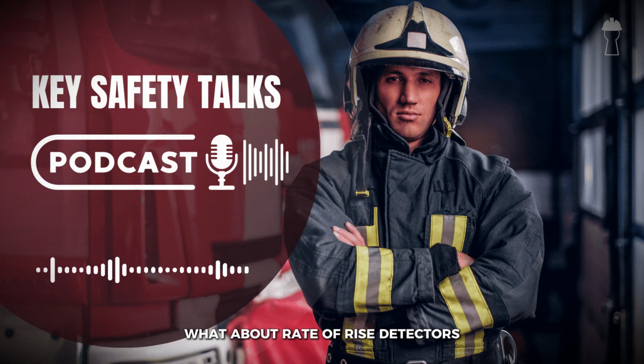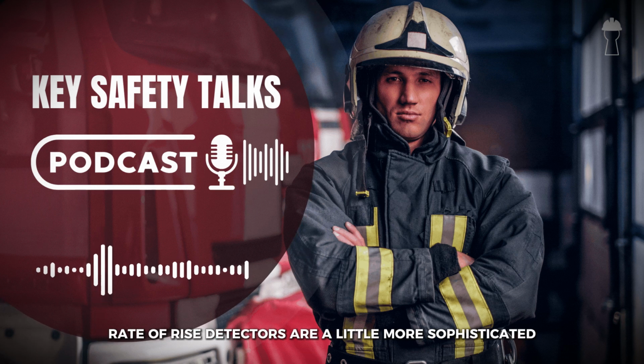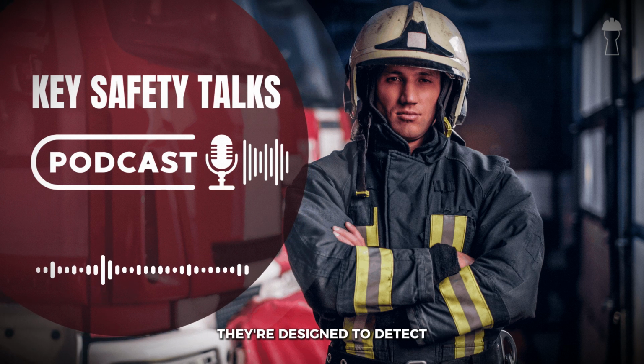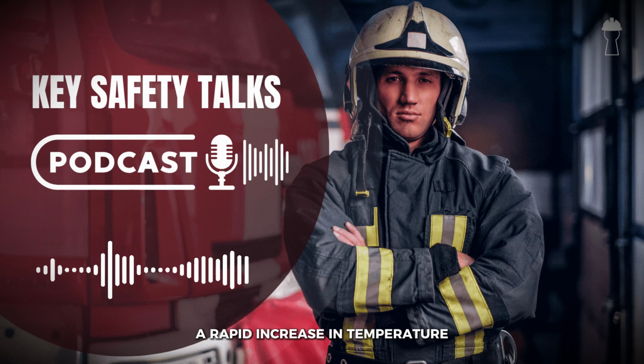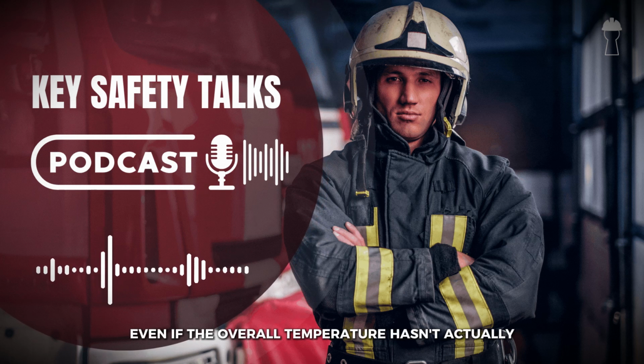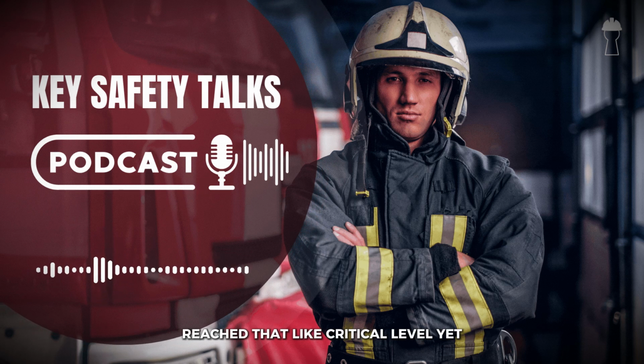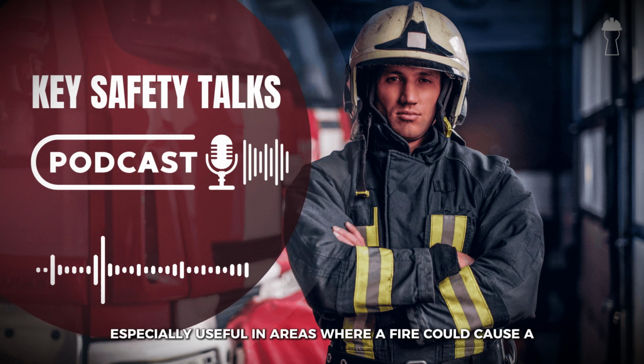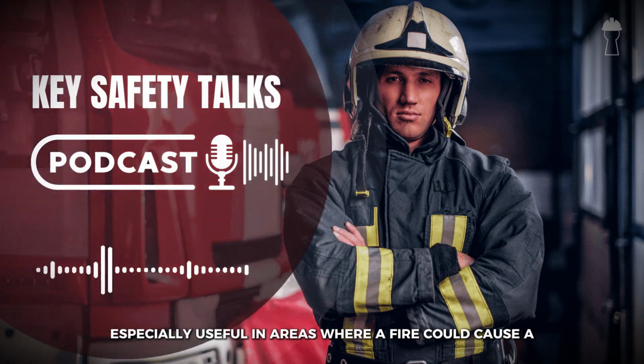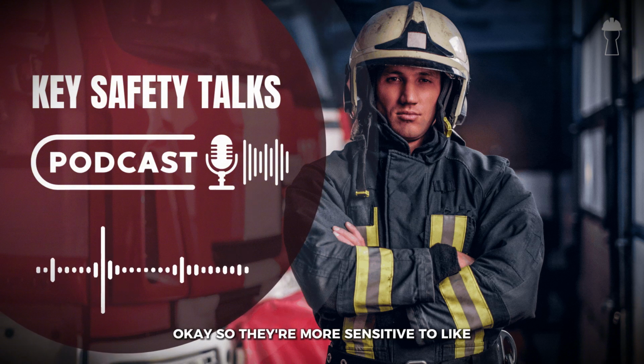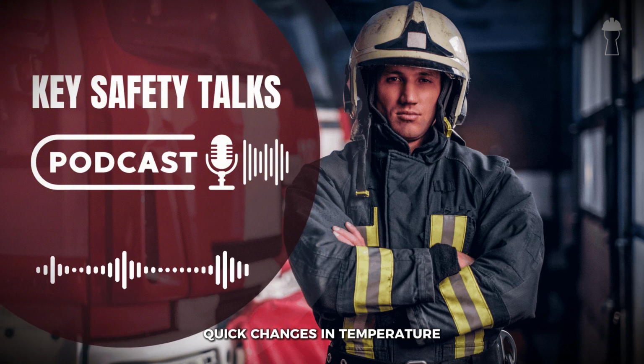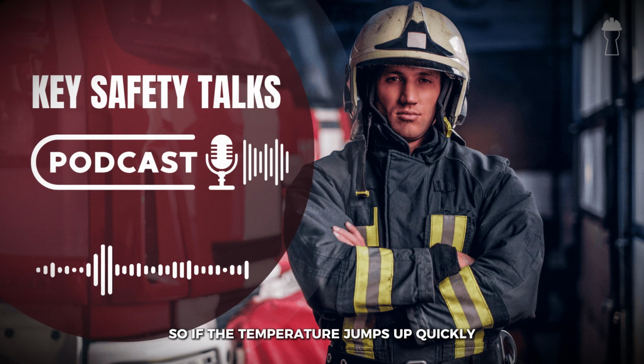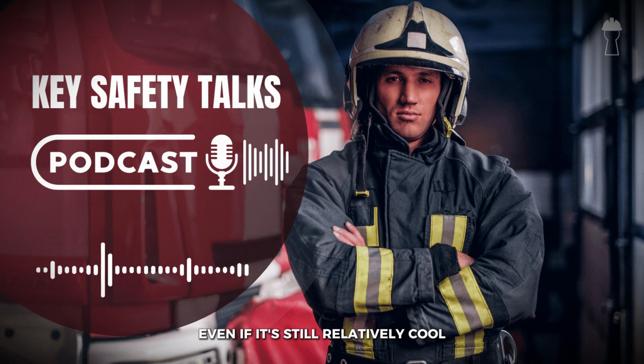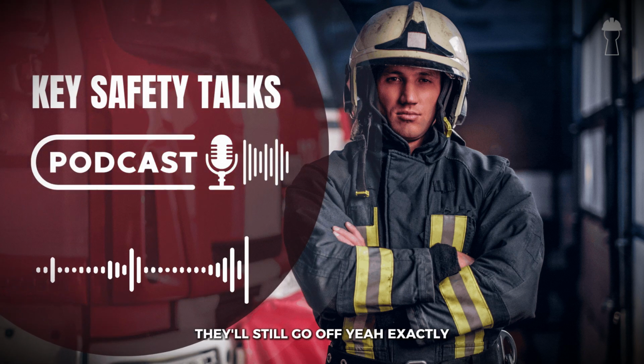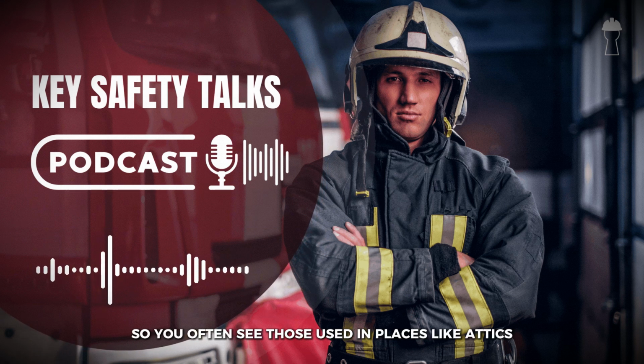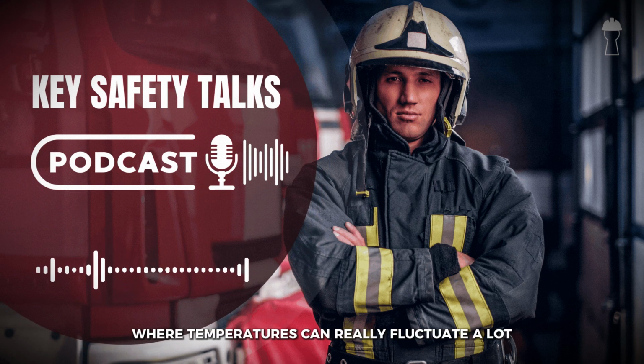What about rate of rise detectors? Rate of rise detectors are a little more sophisticated. They're designed to detect a rapid increase in temperature, even if the overall temperature hasn't actually reached that critical level yet. They're especially useful in areas where a fire could cause a really sudden surge in heat. Okay, so they're more sensitive to quick changes in temperature. So if the temperature jumps up quickly, even if it's still relatively cool, they'll still go off. Yeah, exactly. So you often see those used in places like attics, where temperatures can really fluctuate a lot.